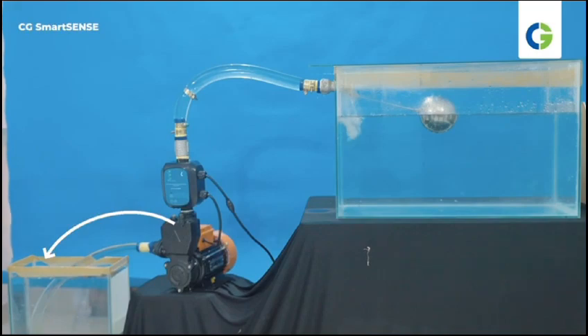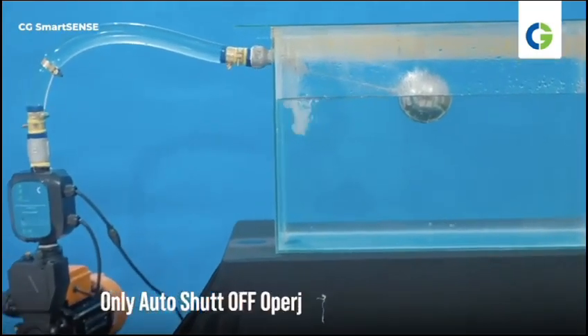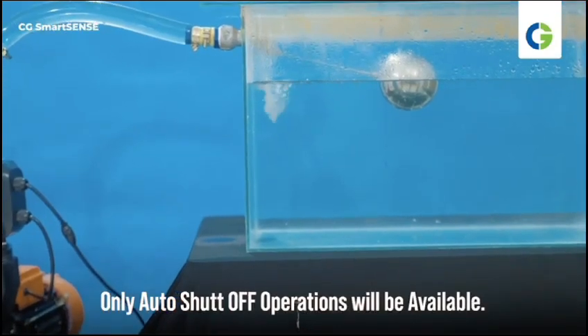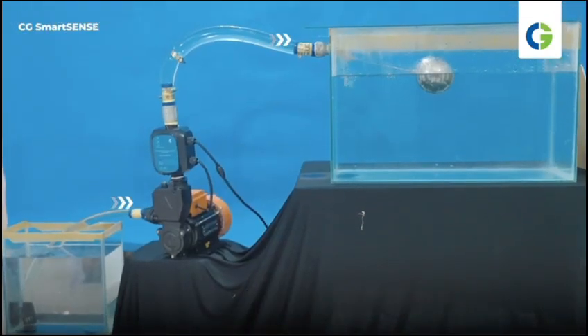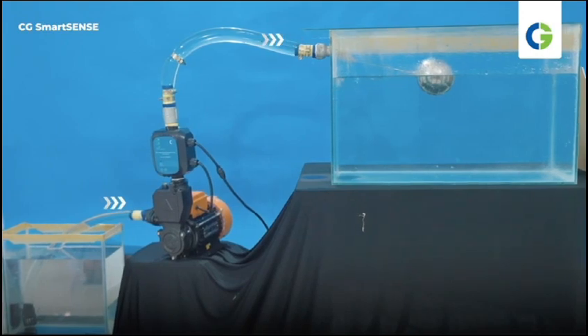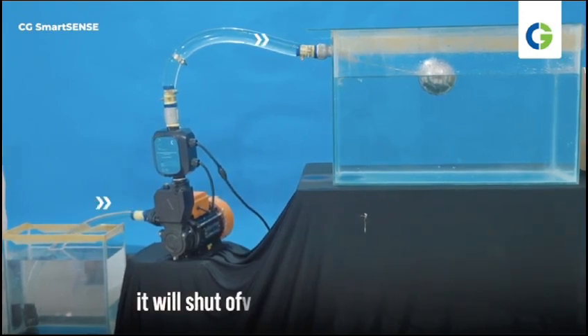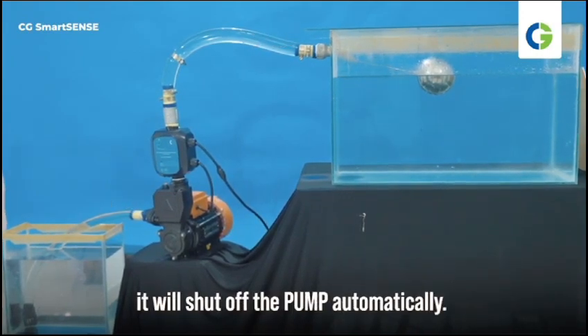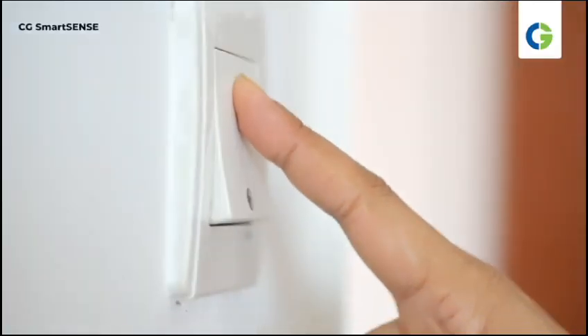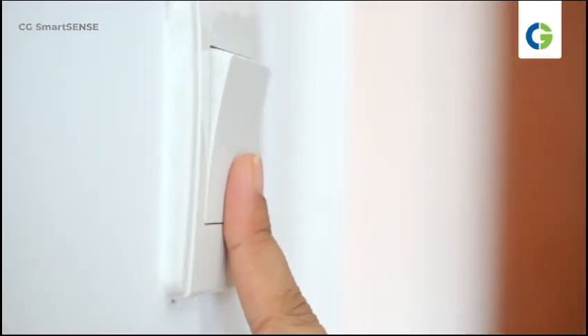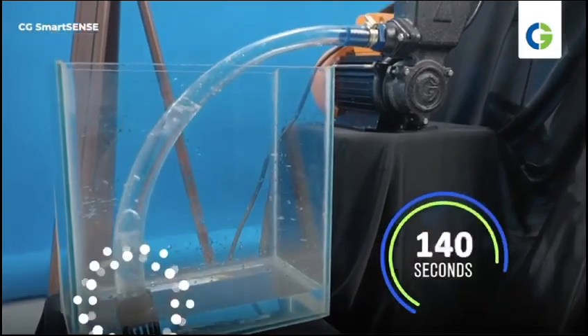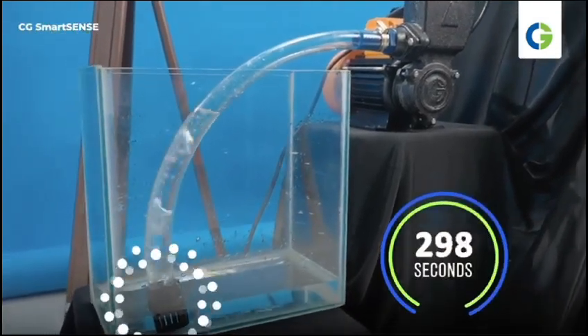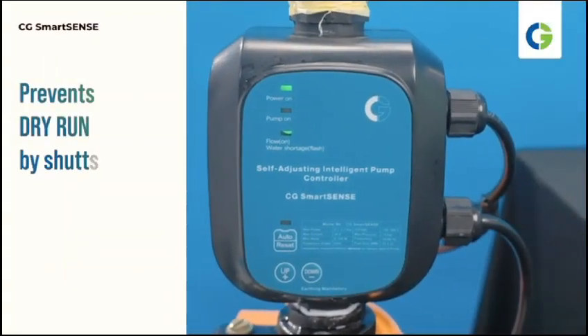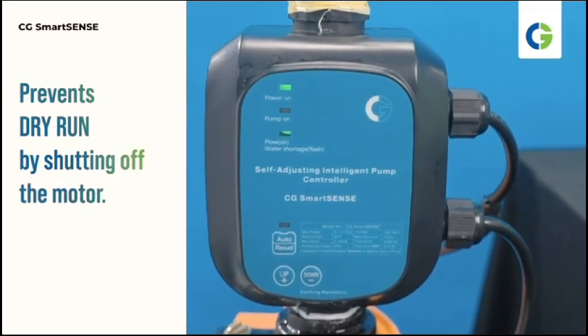Application 2. Pump connected to a sump water reservoir. In this case, only auto shut-off operations will be available. Our cordless water controller senses the water level in the tank. Once the overhead tank is full, it will shut off the pump automatically. To start again, you need to turn off the pump's main power switch and turn it back on. If no water is at the suction pipe, then our pump will keep detecting the water for 300 seconds. Then it will turn off the motor operation to protect it from dry run.